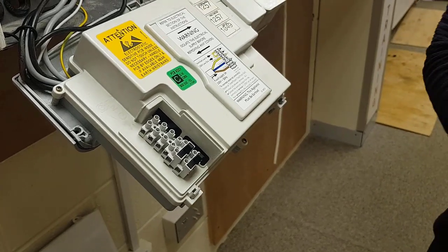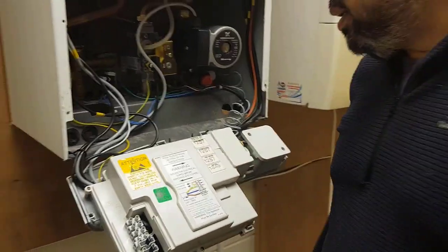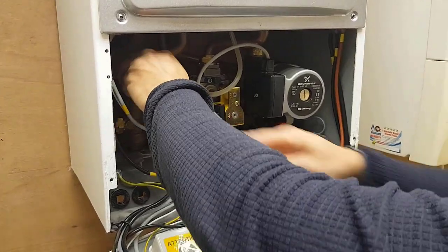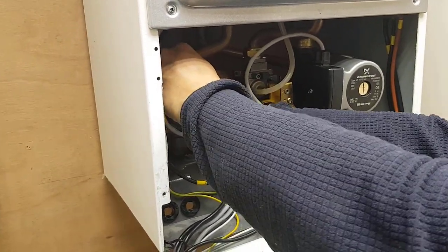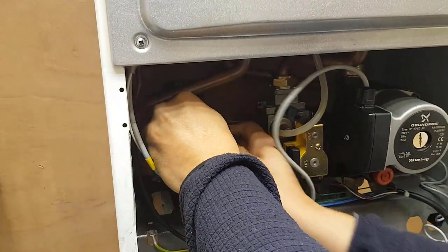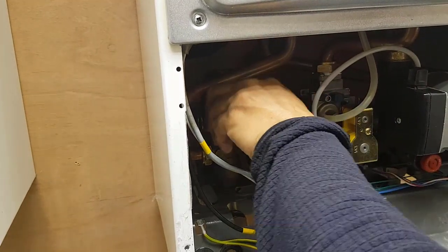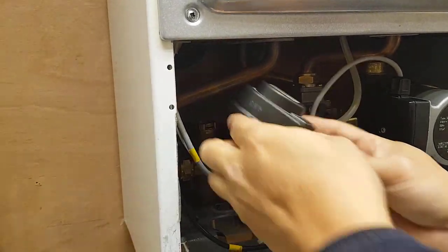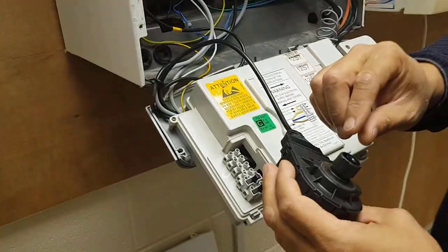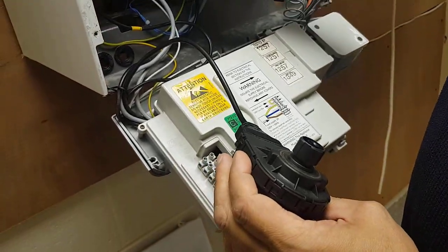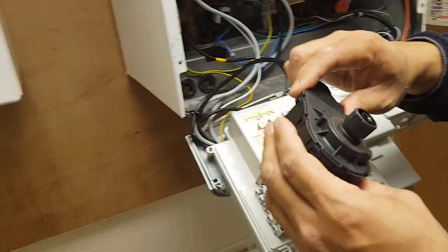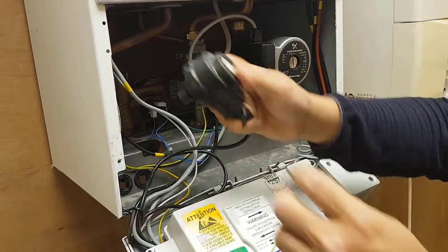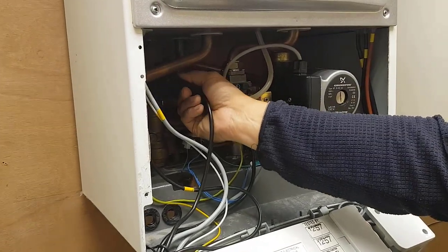So what I'll do is check the actuator motor. There's a pin inside here. Just take the pin out. Just gently lift it up. Just check inside. Oh, I can see a bit of water inside here. Just feel it inside the cartridge. There's water inside here. So it's the actuator motor that's gone. It's the water in the cartridge letting by.